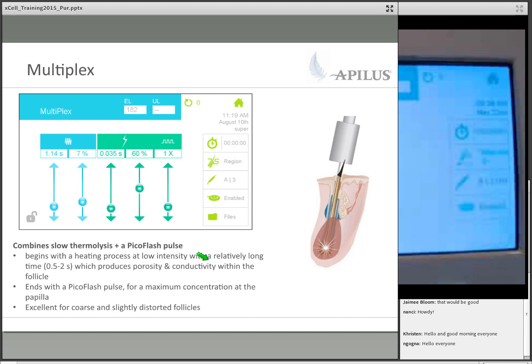Multiplex is kind of different. When we look at a screen with Multiplex, you can see what's going on just by looking at all the different scroll bars, but there's definitely a lot of them. What we have on the left here is slow thermolysis, like the thermolysis that you see in blends. The percent of the slow thermolysis in this case is going to be below 12%. The reason for that is because we're not looking to coagulate with this part of the pulse. What we're looking to do is prepare the follicle.